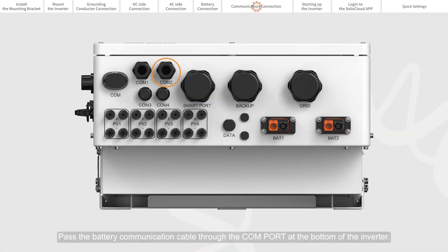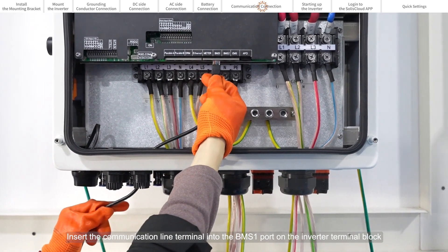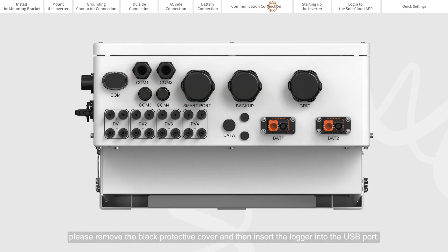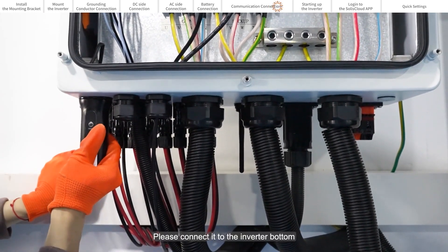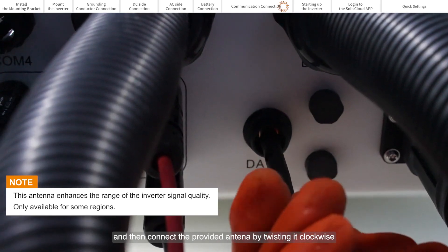Pass the battery communication cable through the COM port at the bottom of the inverter. Insert the communication line terminal into the BMS1 port on the inverter terminal block. The other terminal is connected to the battery BMS port. If you are installing a Solis data logger, please remove the black protective cover and then insert the logger into the USB port. Remove the protective cap on the antenna port and then connect the provided antenna by twisting it clockwise.